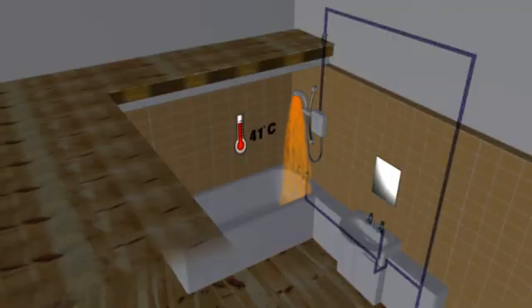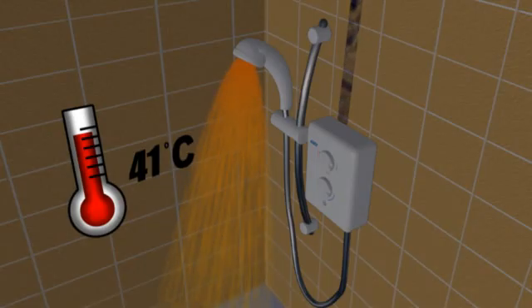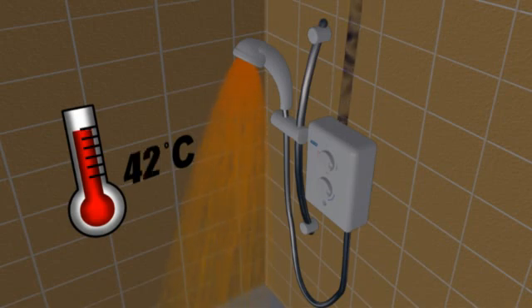If your cold water supply has a large demand from washers, kids, and more, then maybe you should consider a thermostatic electric shower. These showers can maintain the water temperature to within one to two degrees Celsius — not only when your water pressure changes, but also when the incoming temperature of your cold water or electric supply voltage changes.